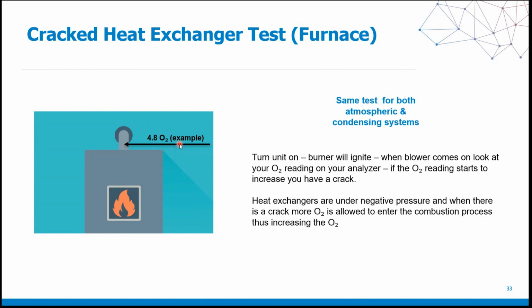Once the fan kicks on, you're going to continue to look at your analyzer. If that oxygen level starts to increase, if it goes to 5.6, 6.4, 7.2, there's your crack. And the reason why is combustion is a sealed process or protocol. And when the fan kicks on, if there's a crack in the heat exchanger, through the negative pressure and entering in through that crack, you are allowing additional oxygen that is not supposed to be in your sealed combustion process.